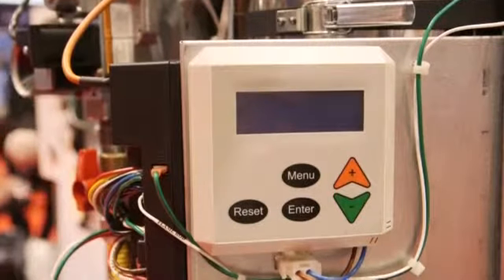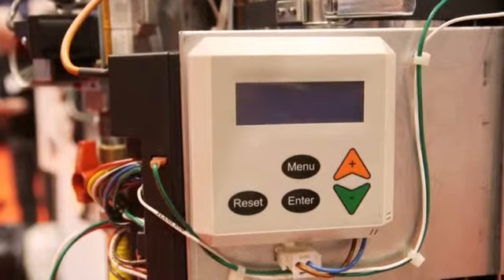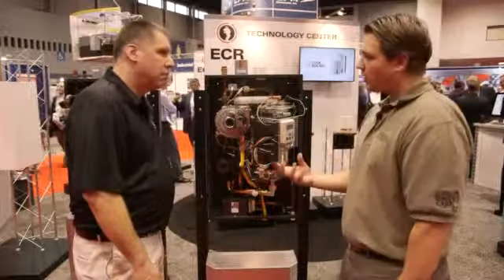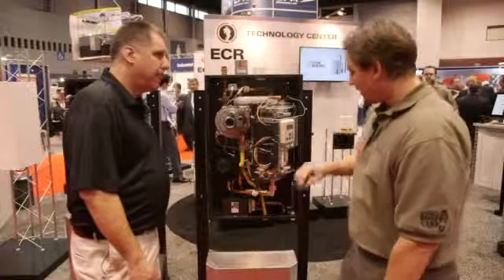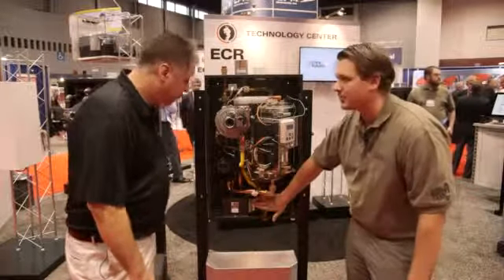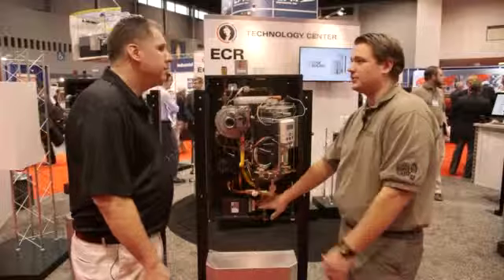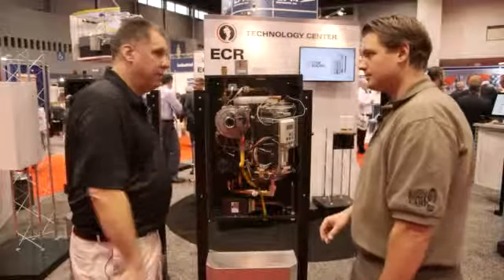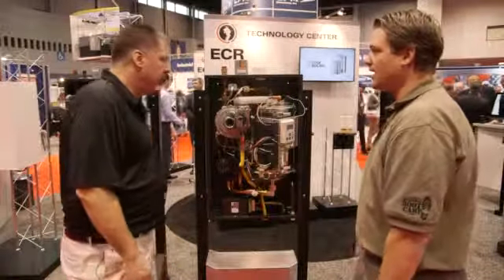Simon, tell me about this control. Does it have outdoor reset built into it? The outdoor reset is built into it. We ship every boiler with a sensor. That sensor gets hooked up down here to our low voltage terminal strip. It'll automatically do the outdoor reset. And just pull thermostat wire to the outside. Thermostat wire to the outside, yep. Very nice.